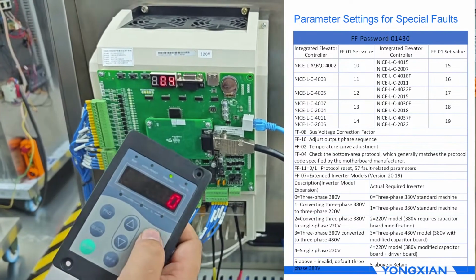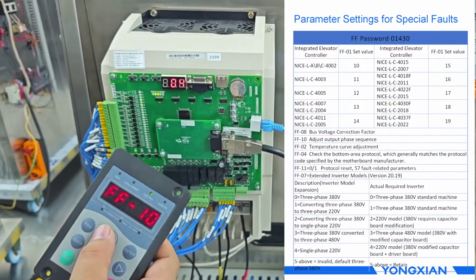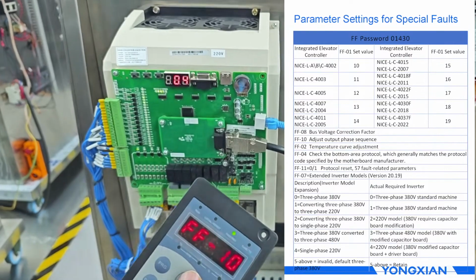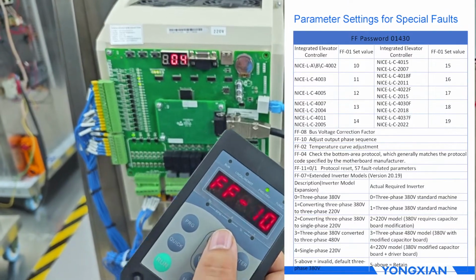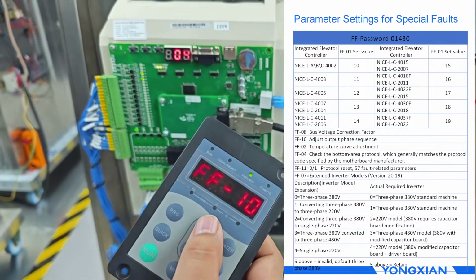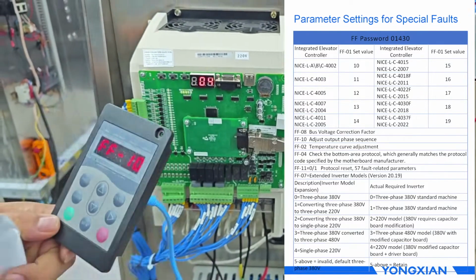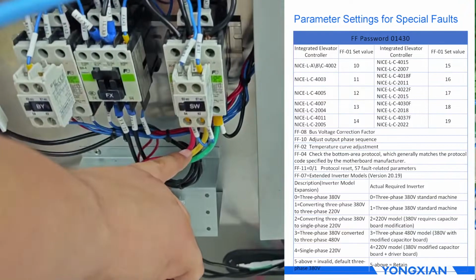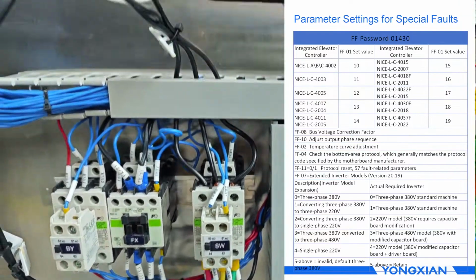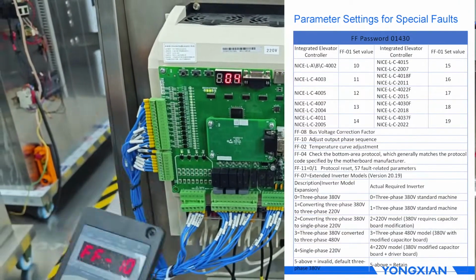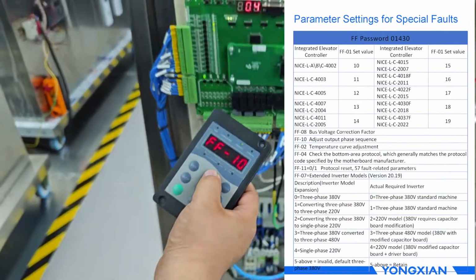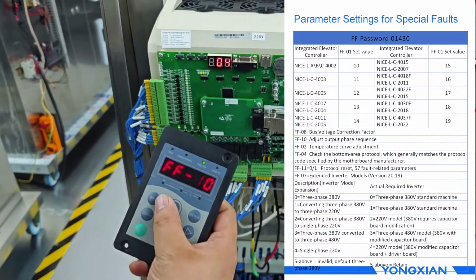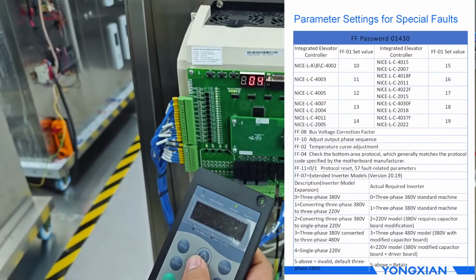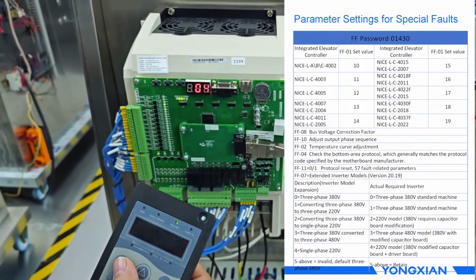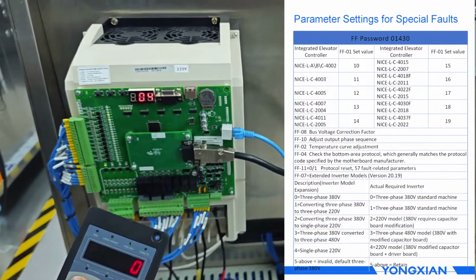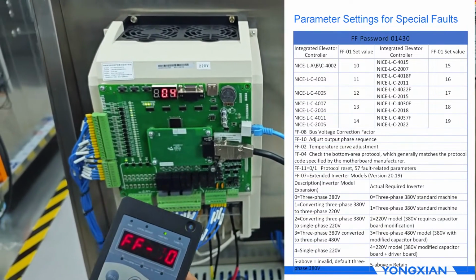FF10 is used to adjust the output phase sequence. Usually, if the output phase wiring of our SW contactor is reversed, we don't need to change the wiring manually. We can set the output order through this parameter so that UVW is reversed.